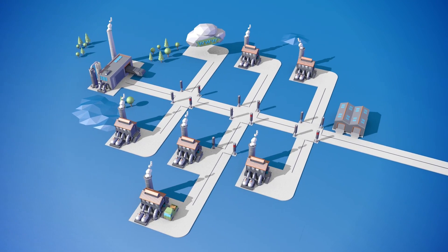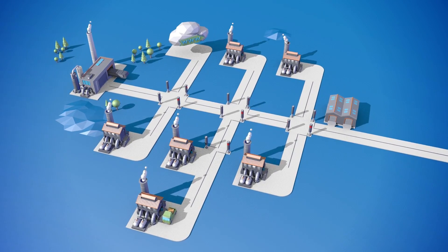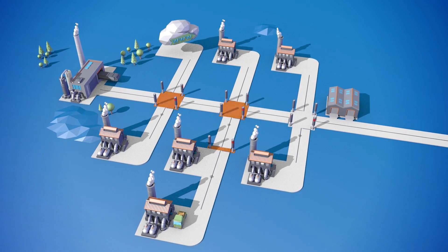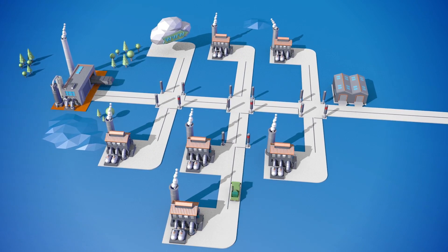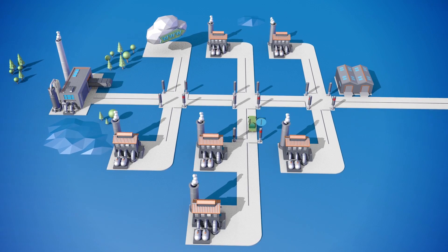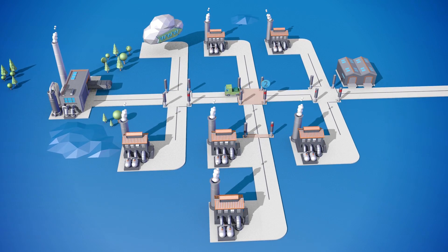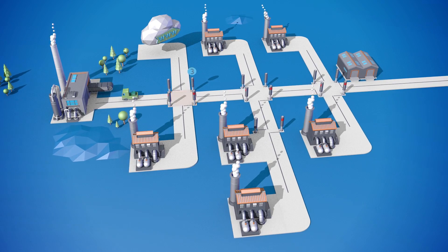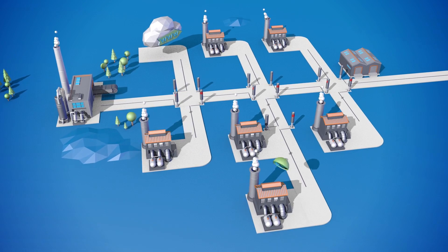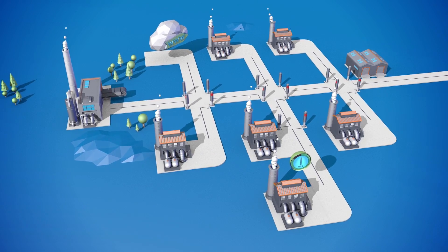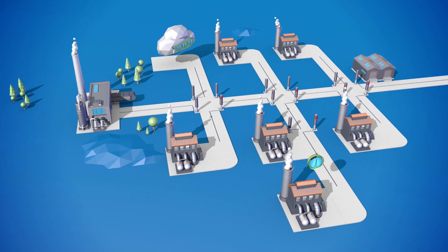Line depth is important here. The line depth specifies the number of transitions between the I-O device and the controller. In other words, how many traffic lights the vehicle passes through on the way to the production facility. When designing a network, it is important to plan the line depth in relation to the level of the update rate.